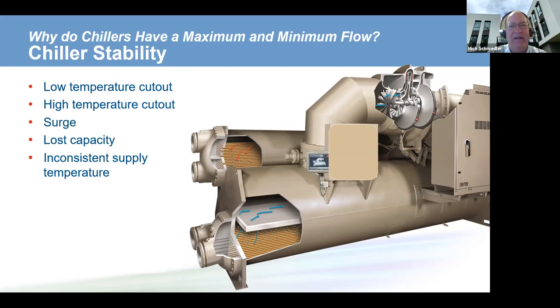It can cause the chiller to surge. And what happens when a chiller surges is the compressor is unable to overcome the pressure difference of the refrigerant between the evaporator and the condenser. And refrigerant actually flows alternately backwards and forwards through that compressor. And a technical service group that I work with tells me, I'm required to tell you, you should not operate a centrifugal chiller in surge for extended periods of time, because you can cause damage to that chiller if you do.